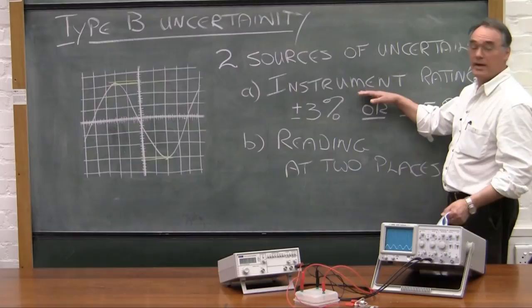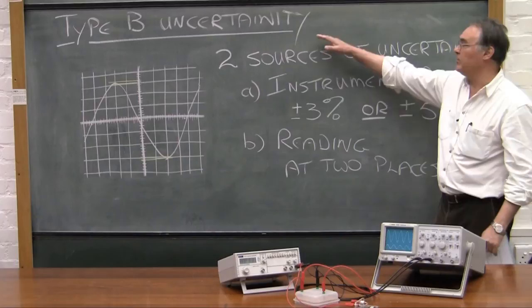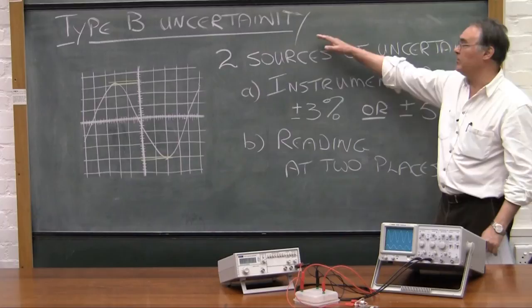So these sources of uncertainty, the instrument rating as well as the readings, all have to be combined to give you the final result of the Type B uncertainty analysis for every measurement that you take.